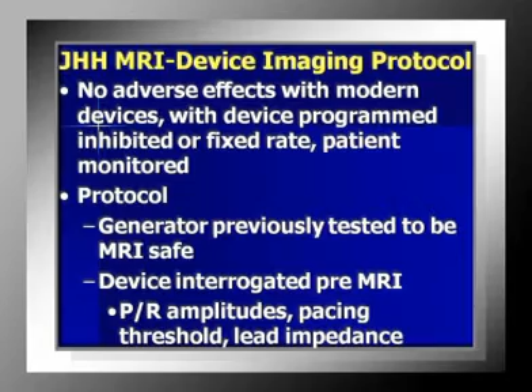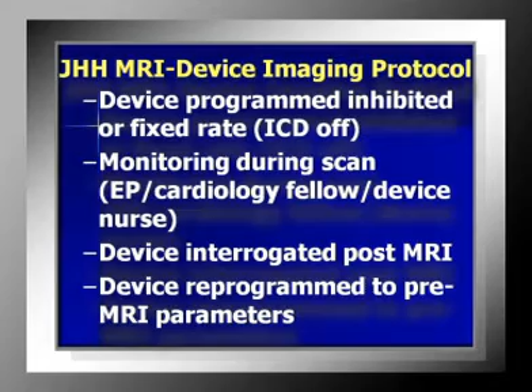So then we have this Johns Hopkins Hospital MR device imaging protocol. Because no adverse effects with modern devices with the device programmed inhibited or fixed rate and the patient monitored have occurred. So the protocol, the generator was previously tested to be MRI safe. It's interrogated pre-MRI. It's programmed to inhibited or fixed rate. There's monitoring during the scan. The device is interrogated post-MRI, and then it's reprogrammed to the pre-MRI parameters.